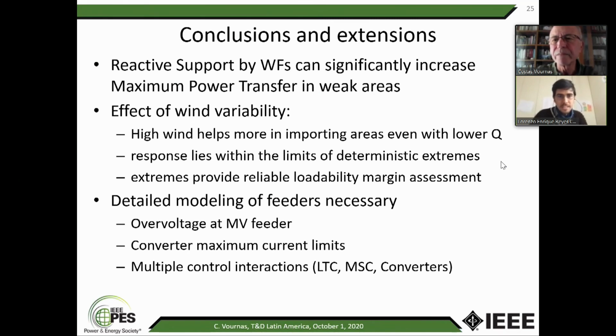So the first question is in terms of voltage dynamic stability, so short term, how the wind park responds to contingencies. Has the system been compromised because of that? No, well, I'm not sure I follow the question, but let me try to say a few words more about how the wind will respond to contingencies. In this case, the contingency was the loss of one unit. The effect on the wind farm was mostly through the voltage. So it directly felt a lower voltage.